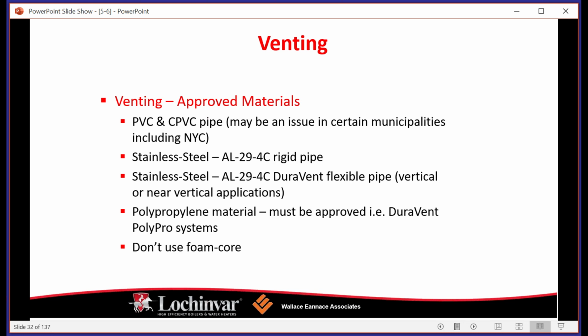Okay, so let me backtrack a little bit. I know I just said that we don't see flue gases that are hot enough to ignite the PVC. Standard solid core Schedule 40 PVC will not be ignited by the flue gases. However, if there is a fire in the boiler plant ancillary to the boilers, Schedule 40 PVC will burn, and when it does burn, it creates toxic gases, which is the reason why it's not able to be used in the 5 boroughs. You don't get that with polypropylene. So polypropylene is kind of in the middle between AL29-4C and PVC.